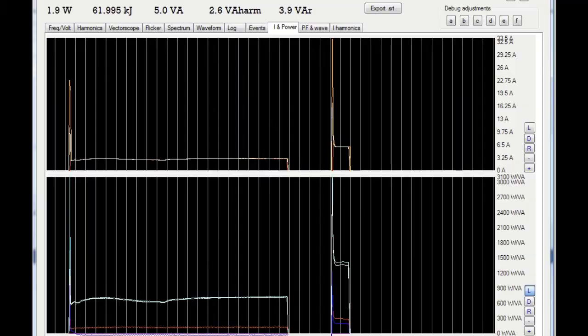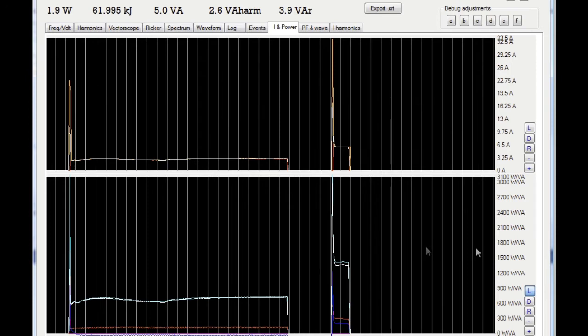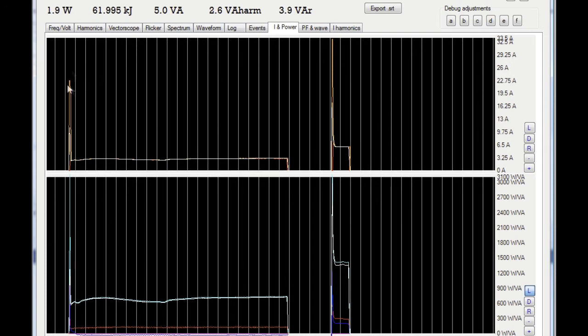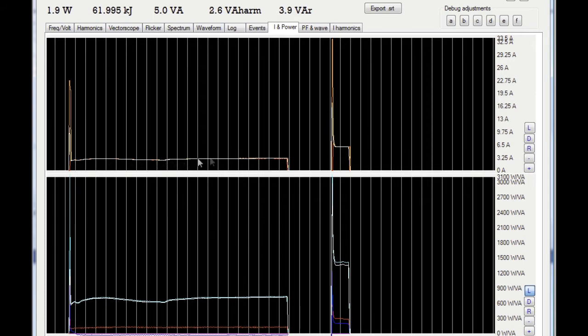Okay, as promised, we're going to look at some current waveforms. But just before we do that, we'll look at these curves. At the top we've got current and at the bottom we've got power. This was recorded during that video clip. This is the switch-on of the AC unit with a peak current consumption of around 20 amps. And here for the vacuum cleaner, peak current of around 33 amps. As you can see, after the switch-on surge, the current stabilises at operating values of around 3.5 amps for the AC unit and about 6.5 amps for the vacuum cleaner.